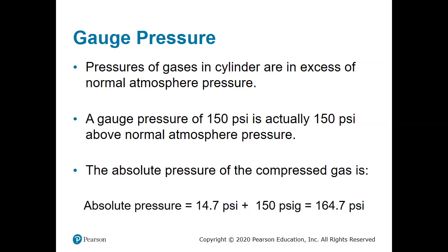That's enough to asphyxiate you. So when we look at, quote, empty tanks, we have to understand that there is still 14.7 psi of whatever that gas is in there. And so we still need to treat the empty container with the same precaution that we treated it when it was full.